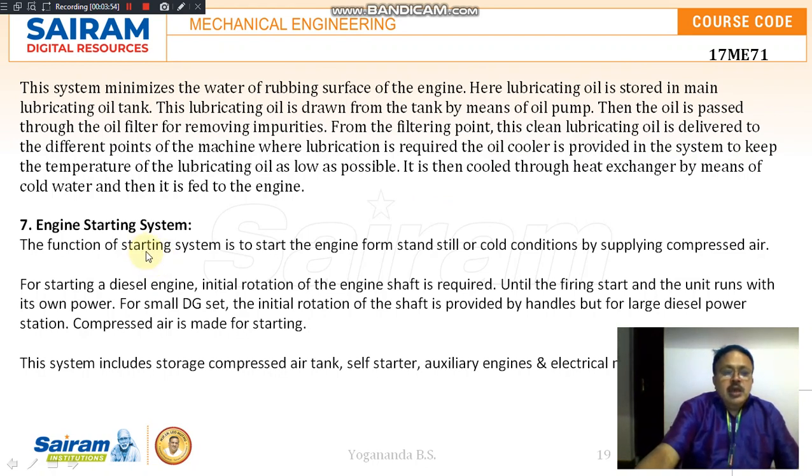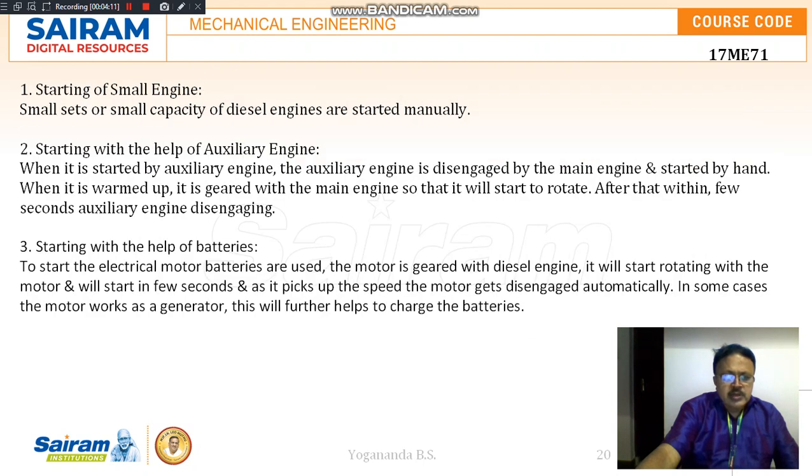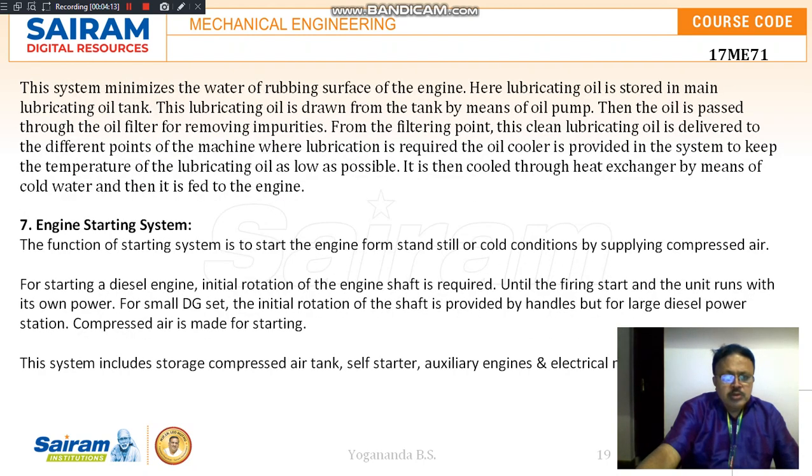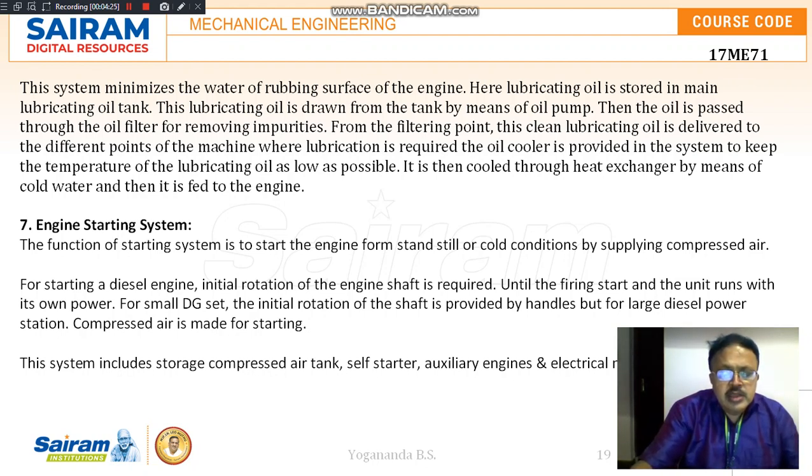Then another question that will be asked is, how do you start the diesel engine? That is the engine starting system. The function of the starting system is to start the engine from standstill, or the diesel engine which is in cold conditions, by supplying compressed air. For starting the diesel engine, initial rotation of the engine shaft is required until the firing starts and the unit runs with its own power.